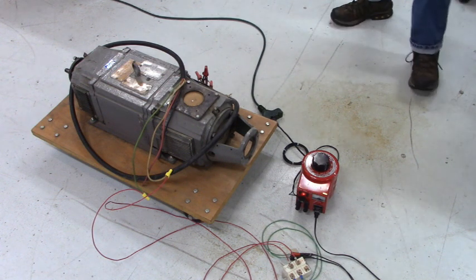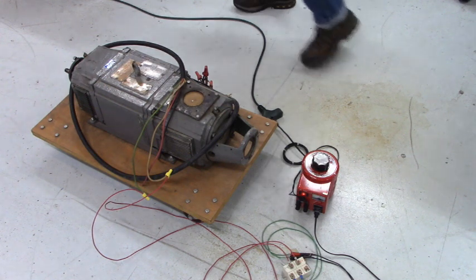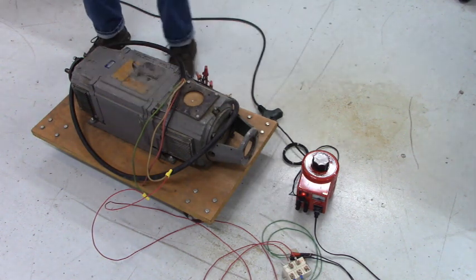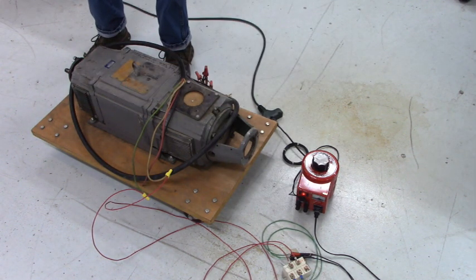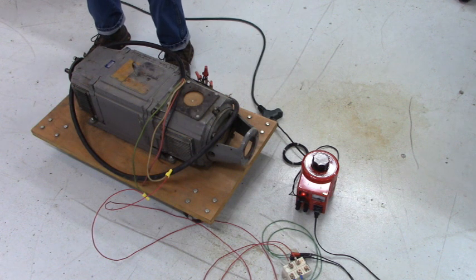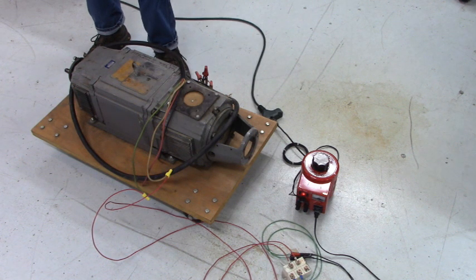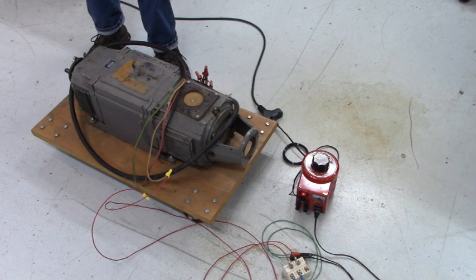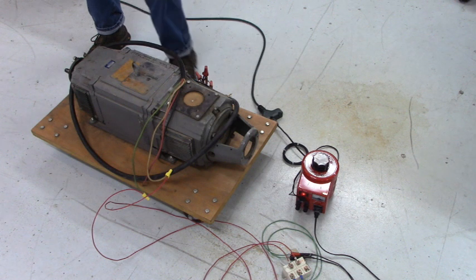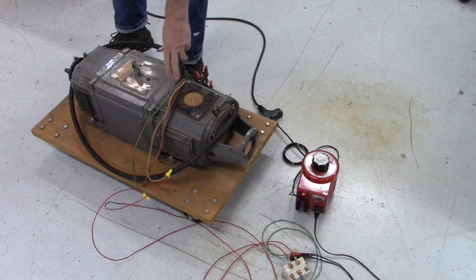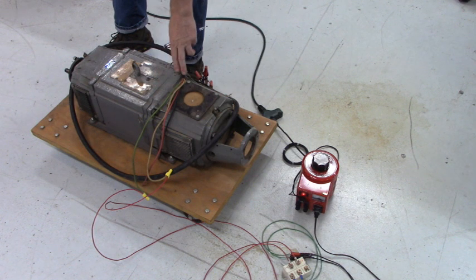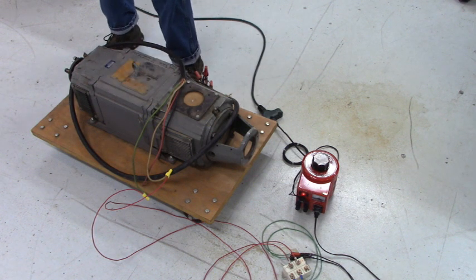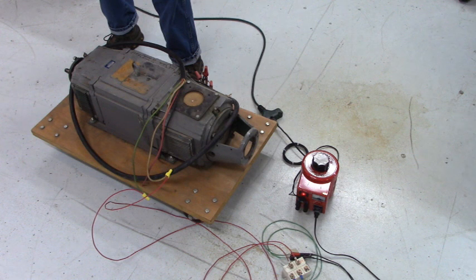Next, this DC motor does not have tach feedback, and every now and then, many times actually, your DC drive will need some kind of feedback. And it is either armature feedback, where the drive looks at the output across the armature, or it will use tach feedback.